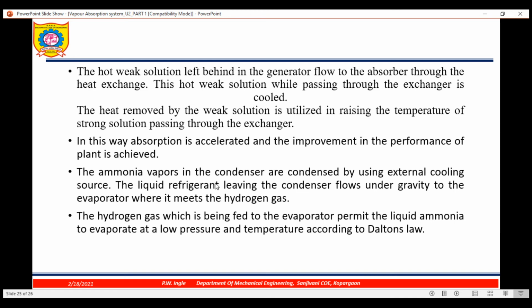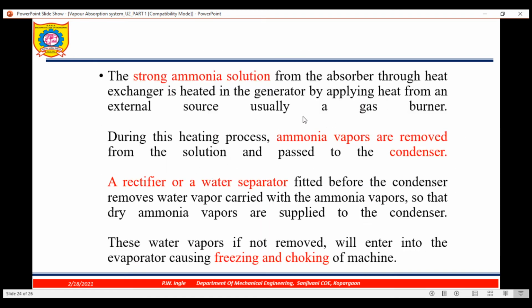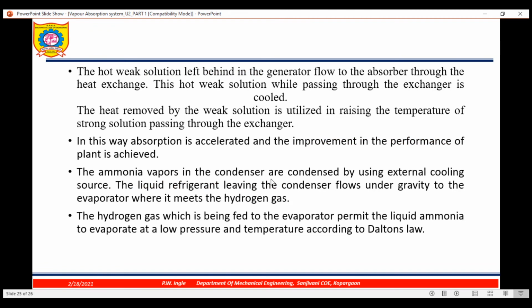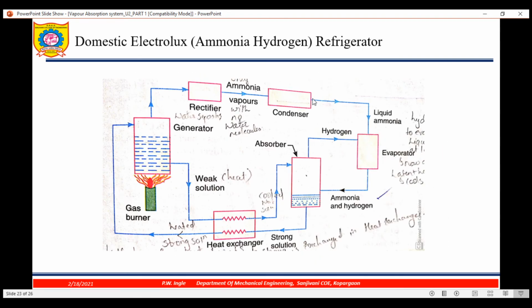Now, the ammonia vapors in the condenser are condensed by using an external cooling source, and the liquid refrigerant leaving the condenser flows under gravity to the evaporator. This is very important: it flows under gravity.